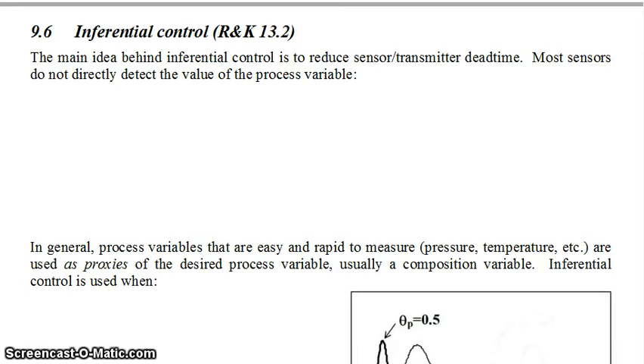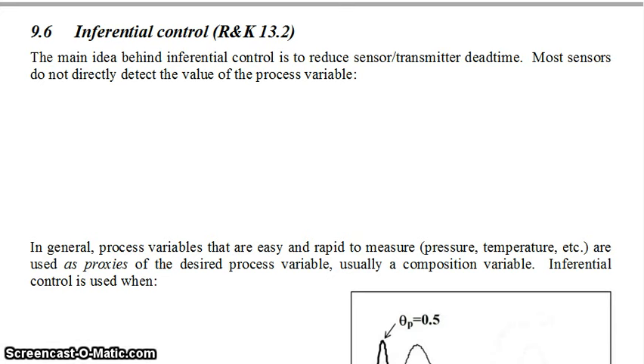We will now talk about another advanced control method called inferential control. Inferential control is essentially just using a model to make one of your measurements a proxy for another measurement. The main reason why you would use inferential control is that the thing you really want to measure is really hard to measure, or measuring it has associated with it a large sensor transmitter dead time. So the idea for inferential control is to reduce this dead time.